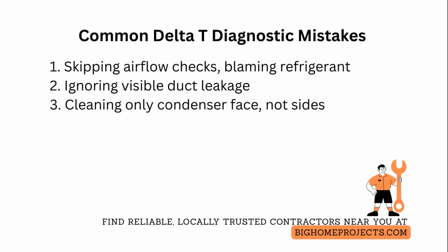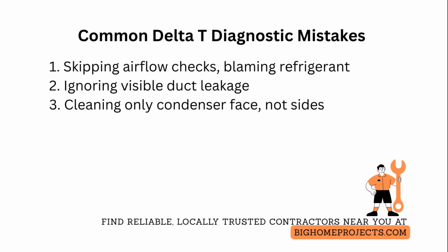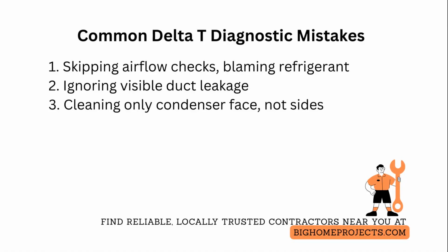A third issue is focusing only on the condenser face while missing side and rear coil blockage and bent fins. Reduced outdoor heat rejection elevates head pressure, narrows temperature split, and strains the compressor.